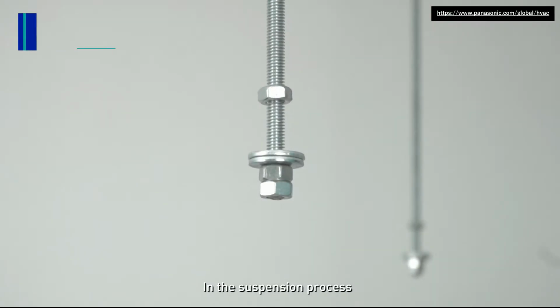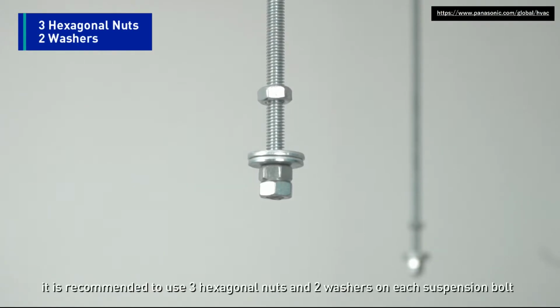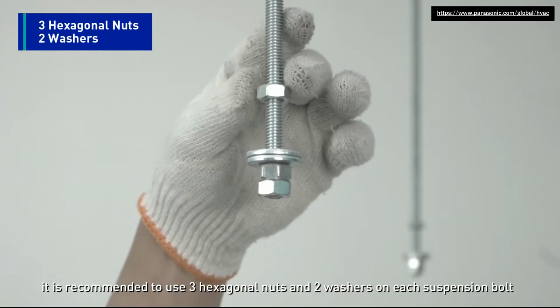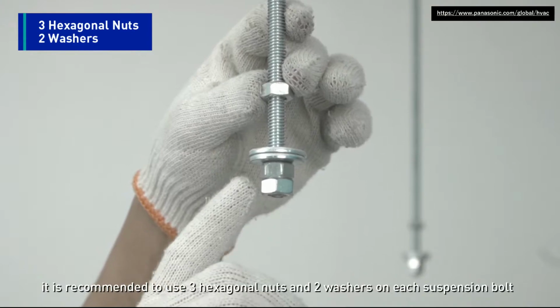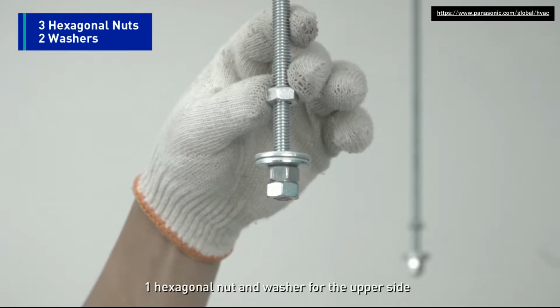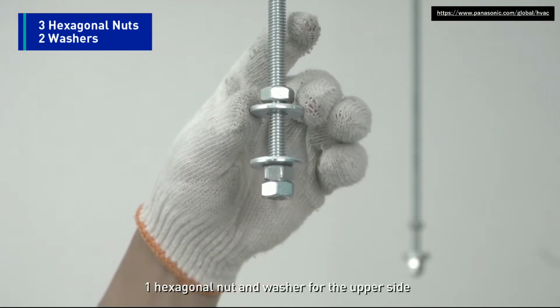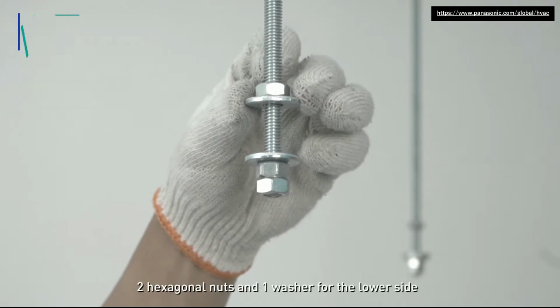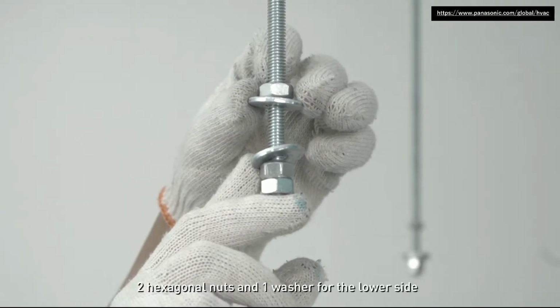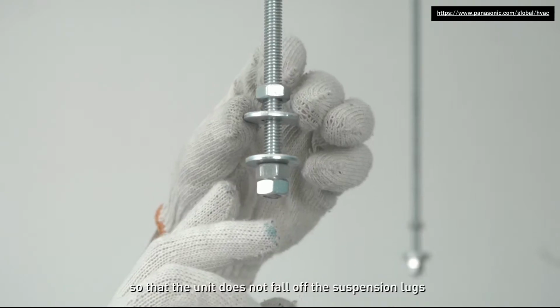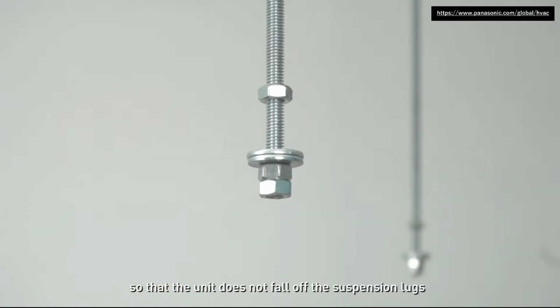In the suspension process, it is recommended to use 3 hexagonal nuts and 2 washers on each suspension bolt. 1 hexagonal nut and washer for the upper side, 2 hexagonal nuts and 1 washer for the lower side, so that the unit does not fall off the suspension lugs.